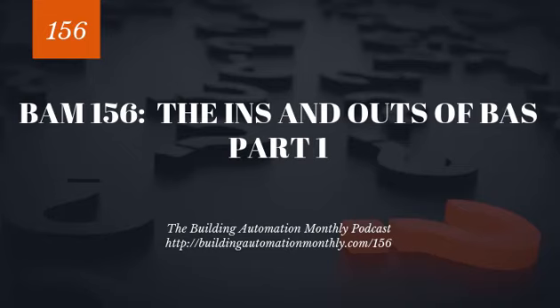The only reason this is important for you to know is if you start to get into complex lab control or operating room control, where you want to have decimal precision of the damper, and you're passing through a bunch of damper positions to do a really tight calculation of reset of discharge air pressure or something, then you want to have decimal precision. You don't want to use whole numbers. You don't want to round that up. So that is why that's important for you to understand.